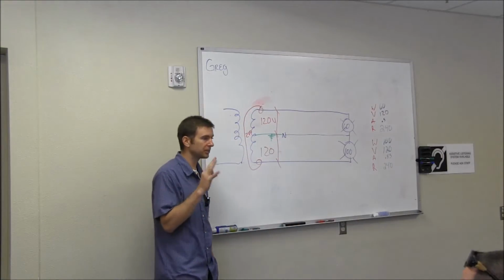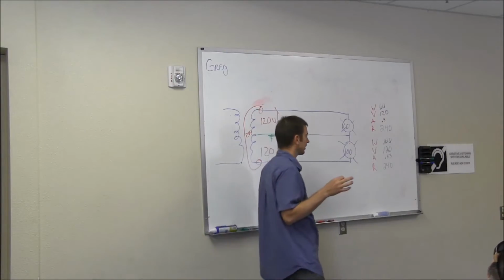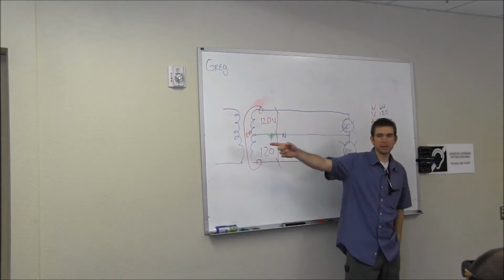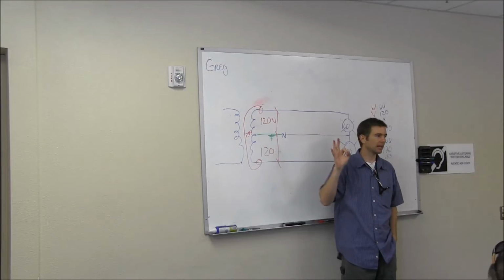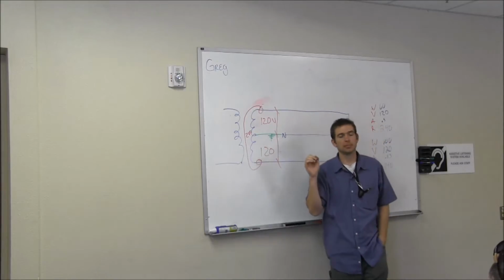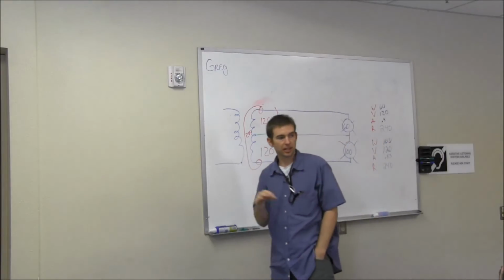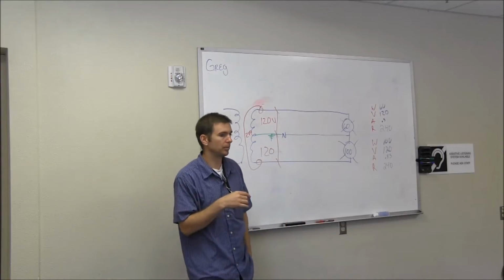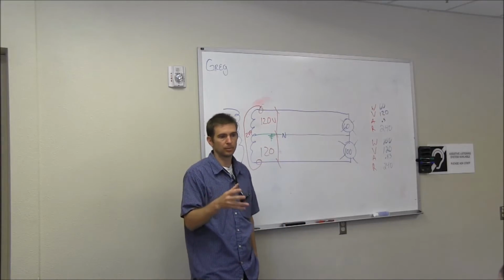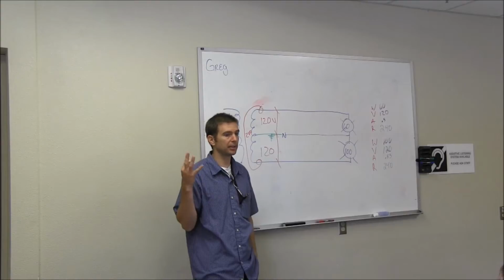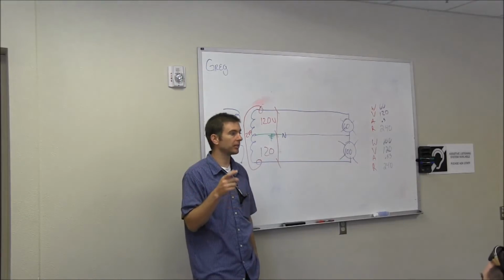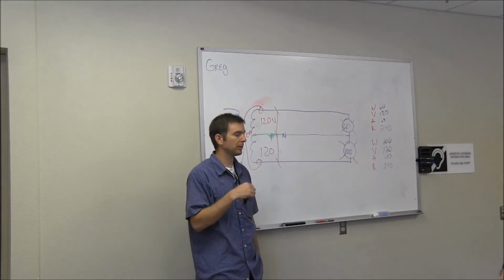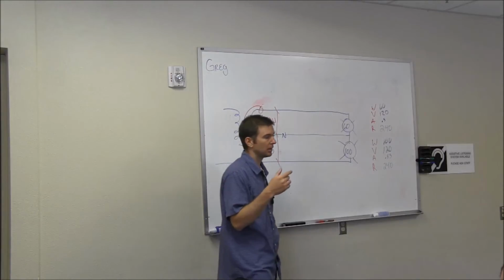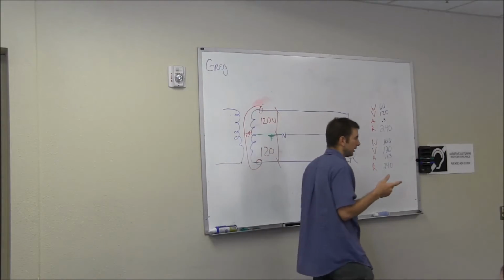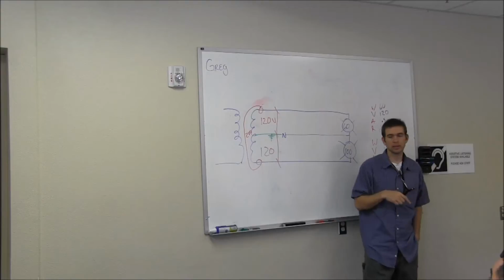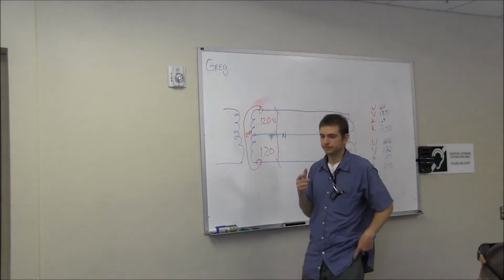So if we have a three-phase circuit, which is what you guys typically have here, you're probably leaving from your panel, you have three hot conductors. You have probably, say, a brown, orange, and a yellow. Are those the colors that you guys have seen out there in the field? Brown, orange, and yellow? White, black, red. Okay, so black, red, blue, because you're going to have three-phase circuits. So you're either going to have black, red, blue, or brown, orange, and yellow. Brown, orange, and yellow is a higher voltage, 277/480, and black, red, blue is 120/208/240.